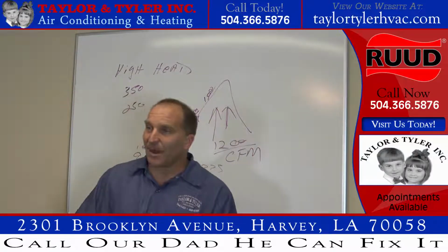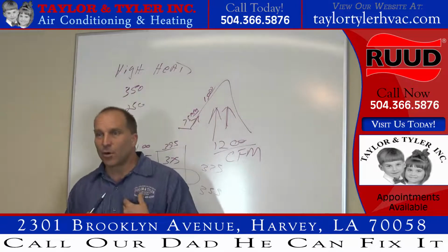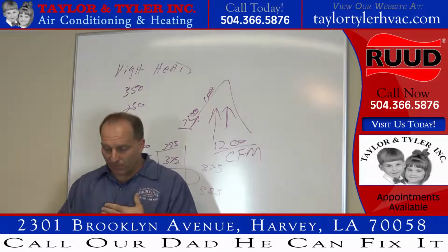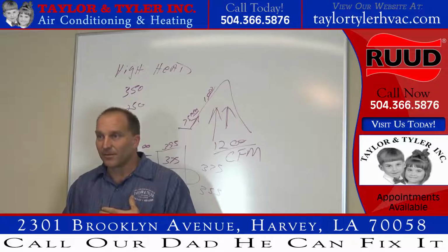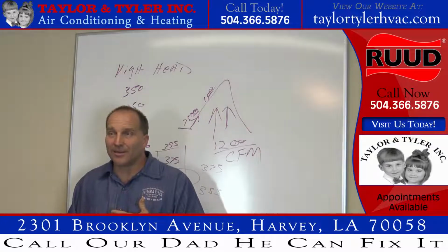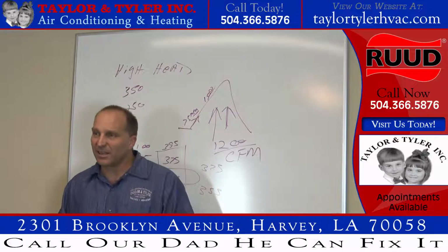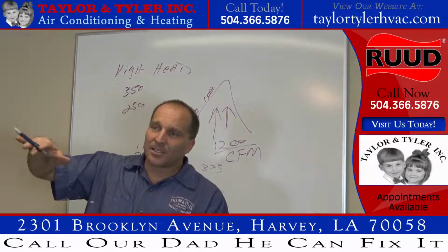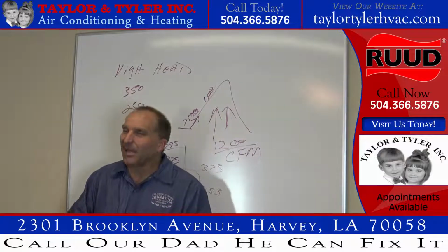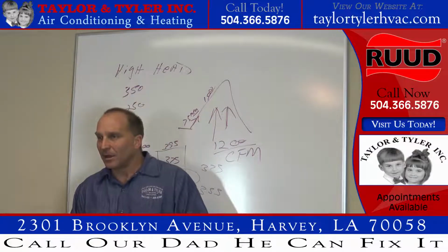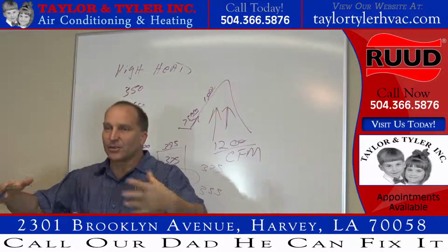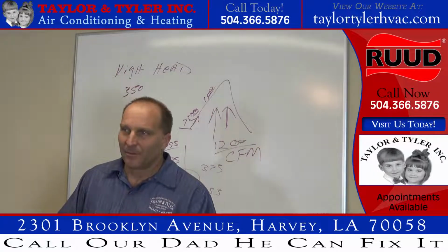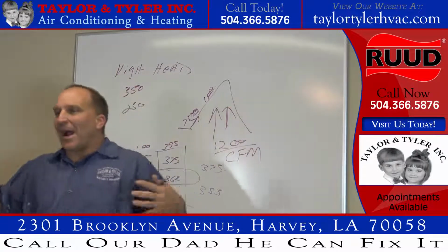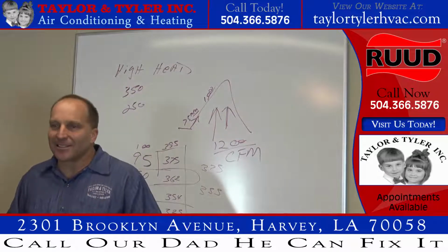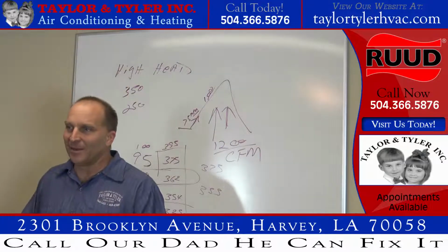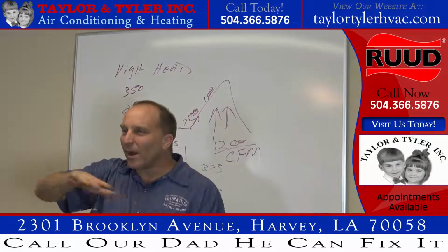So in this case, I keep adding refrigerant into the system, and I have no clue. There is a restriction before my gauge. Can't read it. If you can't read it, can you tell what it is? The only thing that was giving it away a little bit is my subcooling before it got to my gauge was really high, okay? And then my condenser was not blowing out any warm air because the refrigerant inside the condenser was so backed up that it wasn't getting hot because it wasn't picking up any heat from anywhere, right? So my condenser's blowing kind of cool air out of it.